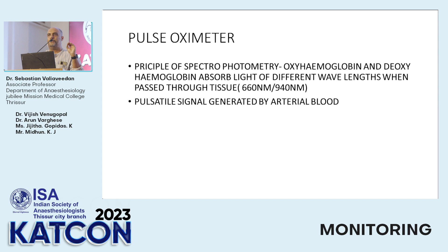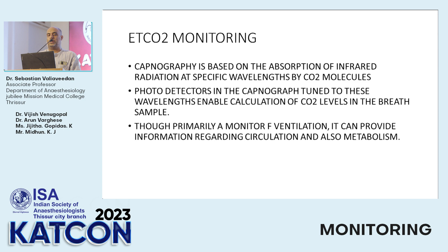Now, EtCO2 monitoring, the capnography is based on, again, absorption spectrometry of the infrared radiation at specific wavelengths by CO2 molecules. It's a similar principle. Photodetectors in the capnograph tuned to these wavelengths enable calculation of CO2 levels in the breath sample. So the CO2 molecules in the expired air will absorb the light at a particular wavelength, just like the pulse oximeter, and that is again used to calculate the fraction of EtCO2, and it is expressed as a numerical value. Though it is primarily a monitor of ventilation, it can provide information regarding circulation and also metabolism. That is, if the pulmonary circulation, the cardiac, the systemic circulation and all are depressed, it will show in the end-tidal CO2 value because the transport of carbon dioxide will be affected. And it also throws light on body metabolism, hypermetabolic conditions and all, CO2 production will increase. So that is about EtCO2 monitoring.